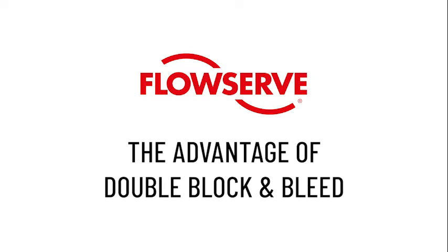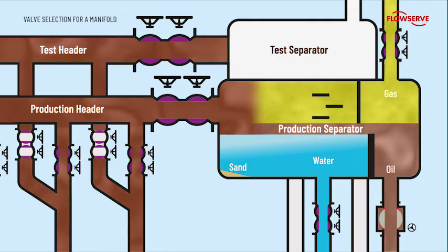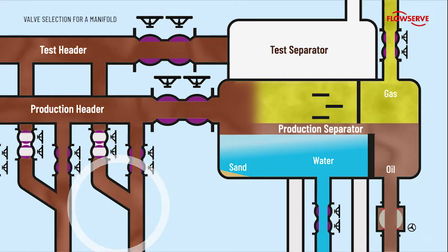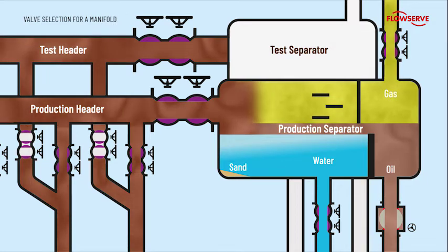The advantage of double block and bleed. If properly designed, manifolds can also be used for isolating specific flow lines from pressure in the headers, allowing for flow line maintenance or the connection to new wells to be completed without the need for a plant to shut down.